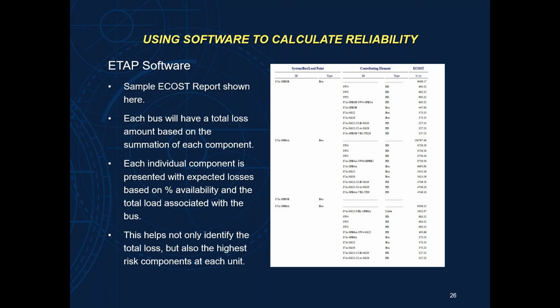The second one, SPB4A, has an E-cost, which is your losses, of $138,000 per year on average based off of the reliability calculation, as opposed to the other 2 buses, 6A and 3B, which are less than $10,000 a year. This will help us look at our system and say, where do we get the biggest bang for our buck? Well, let's do a reliability upgrade on system 4A, and we can get that number down significantly. And every bit we lower that number is more money in our pockets for our facility moving forward on a yearly basis. So this is a great tool for us to use.